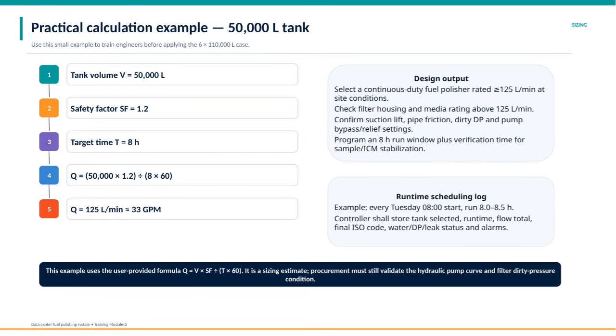The target runtime for polishing is set at 8 hours, which allows for consistent fuel quality maintenance. Using these values, we calculate the flow rate Q by multiplying the tank volume by the safety factor, and then dividing by the total minutes in the target time, 8 hours times 60 minutes. This gives us a flow rate of 125 liters per minute, approximately 33 gallons per minute. From this calculation, the design output is to select a continuous duty fuel polisher that can operate at or above 125 liters per minute at site conditions.